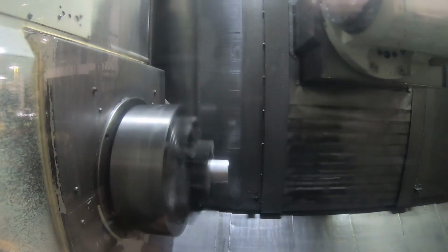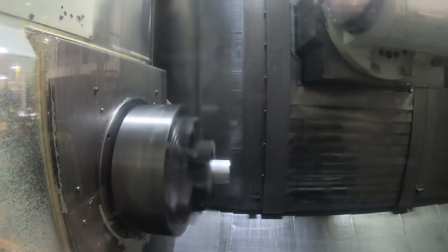And around 600 RPM, it would change windings on the motor. I don't know if you got a bad reflection here. Maybe if I get closer, that'll go away. It would oscillate. It would switch the windings, and it would try to speed up, but it couldn't, and the motor would just be coasting down. Then it would hit the low speed, and it would pull that contactor back in for the star or Y windings, and it would start back up and speed back up, and then it would hit the change on the relays, and it would keep oscillating back and forth, no alarm. So let's see what happens.